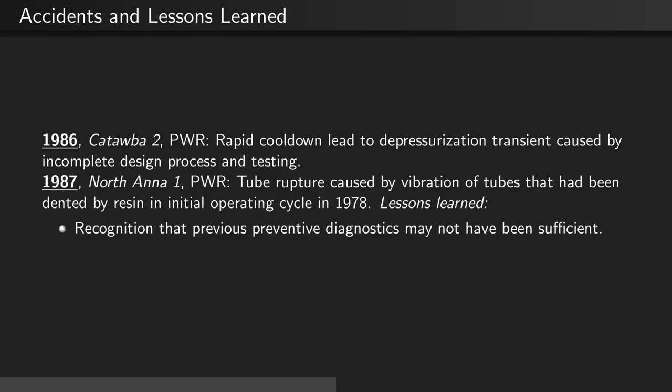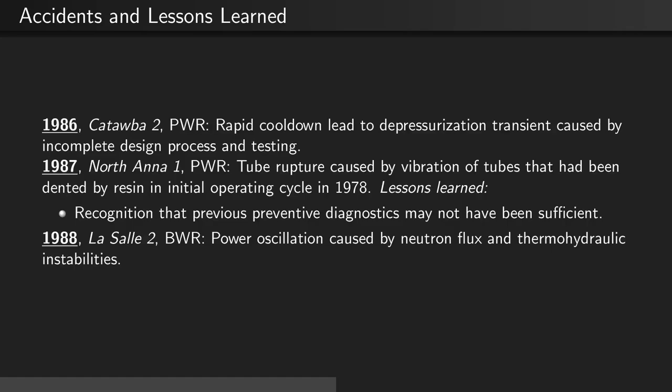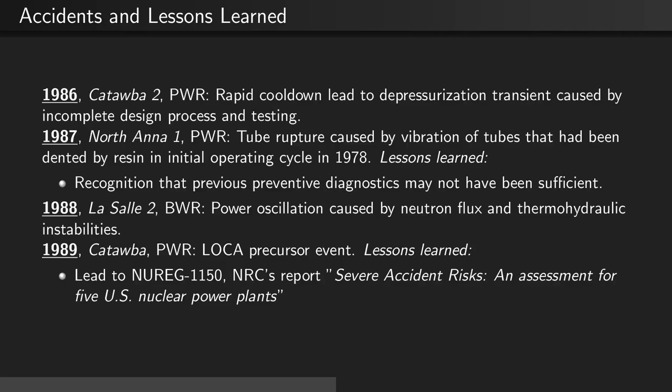In 1987, at North Anna 1, a PWR, a tube ruptured, caused by vibration of tubes that had been dented by resin in the initial operating cycle back in 1978. This caused recognition that previous preventative diagnostics were not sufficient to predict this problem. In 1988, at the LaSalle II boiling water reactor, there was a power oscillation caused by neutron flux and thermohydraulic instabilities — the flux profile and heat profile were not flat enough. In 1989, at Catawba, there was a loss of cooling accident precursor event, which led to the Nuclear Regulatory Commission's 1150 report on severe accident risks at five different power plants.